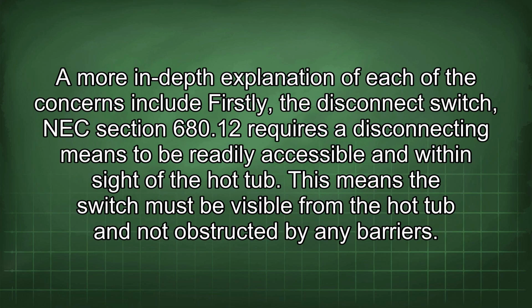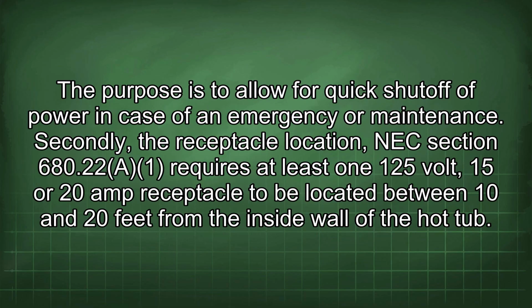A more in-depth explanation of each of the concerns include firstly, the disconnect switch. NEC section 680.12 requires a disconnecting means to be readily accessible and within sight of the hot tub. This means the switch must be visible from the hot tub and not obstructed by any barriers. The purpose is to allow for quick shut-off of power in case of an emergency or maintenance. Secondly, the receptacle location. NEC section 680.22a requires at least one 125V, 15 or 20 amp receptacle to be located between 10 and 20 feet from the inside wall of the hot tub.